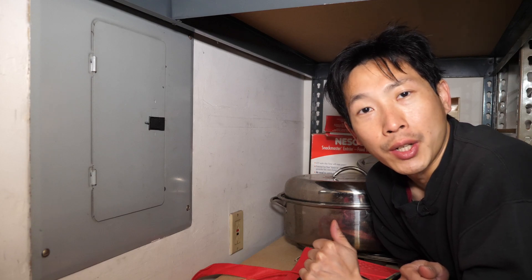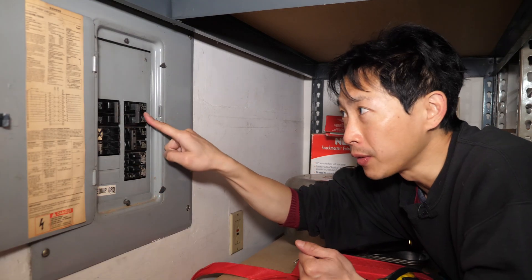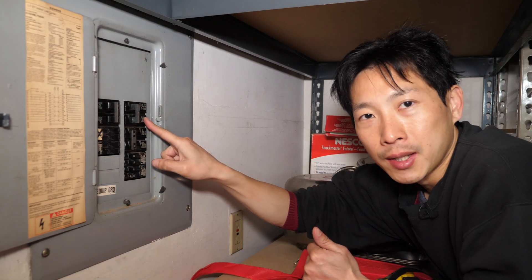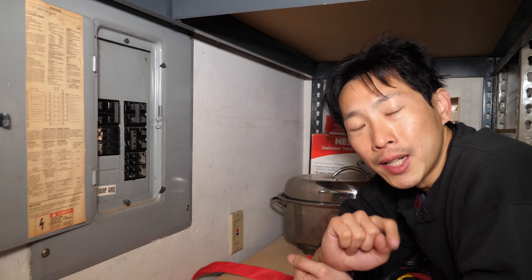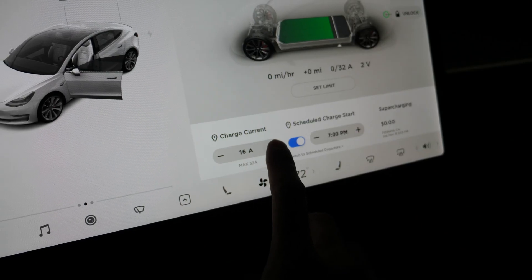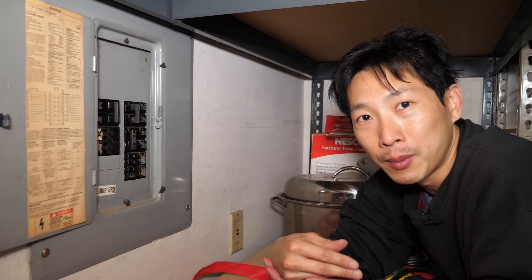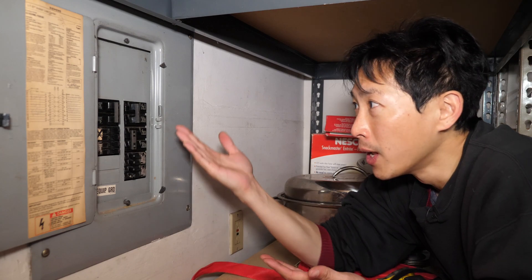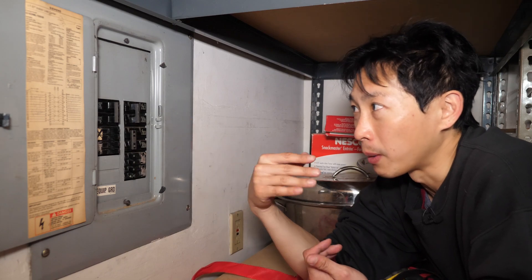Today I'm going to show you how to change a circuit breaker. Here's my breaker panel. This is the 50 amp breaker that goes to charge my car — it's 50 amps, two poles, 220 volts. When you charge, it can charge up to 32 amps, but it keeps tripping. Even after reducing the amperage in the car down to 16 amps, it's still failing. So given that it's a 50 amp breaker, there's obviously something wrong with the circuit breaker.